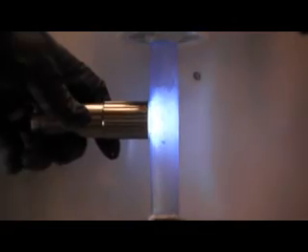As you can see, this is a sight glass, but after a while of being exposed to calcium hypochlorite, there is a discoloration that begins to form inside the tube. So all you need to do is go ahead and order another one from us. They're not very expensive at all, and we can get that replaced for you as part of your preventative maintenance.